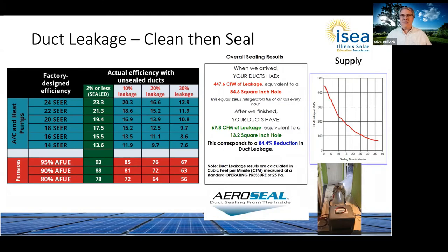When people install ductwork, they don't really seal it well. So look at this: if you have the best air conditioner you could get, a 24 SEER unit, but you have leakage in your ductwork, it knocks that efficiency down. Even minimal leakage drops it to 23.3. At 10% leakage, it goes to 20.3. At 20% leakage, which is extremely common, it's 16.6. At 30% leakage—and yes, ducts really can leak that much—that 24 SEER unit becomes just 12.9.